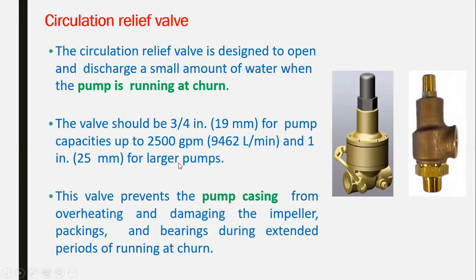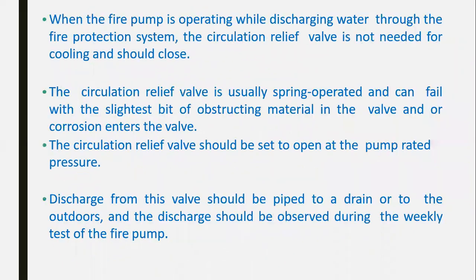This valve functions when the pump is running on the churn position. Churn means the pump is running but without any discharge from the sprinklers. When the pump is operating and discharging water through the fire protection system, the circulation relief is not needed for cooling and should be closed. So it is not operating. It functions only when the pump is running and there is no discharge.